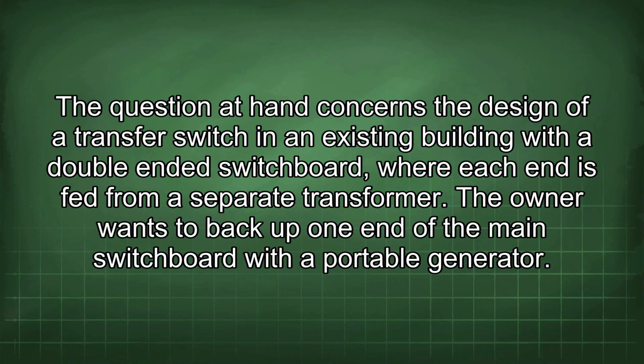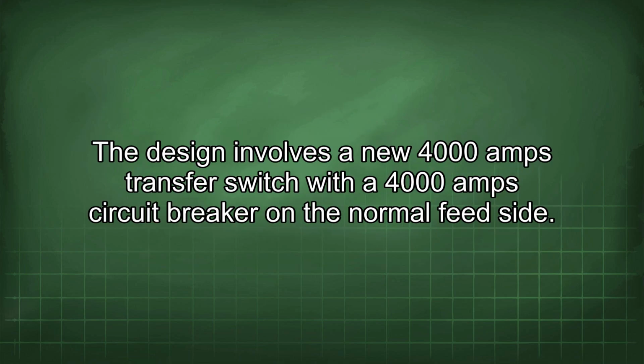The question at hand concerns the design of a transfer switch in an existing building with a double-ended switchboard, where each end is fed from a separate transformer. The owner wants to back up one end of the main switchboard with a portable generator. The design involves a new 4000 amp transfer switch with a 4000 amp circuit breaker on the normal feed side.